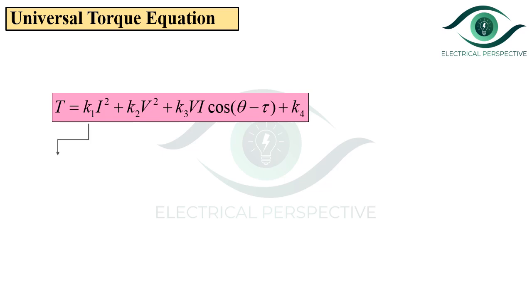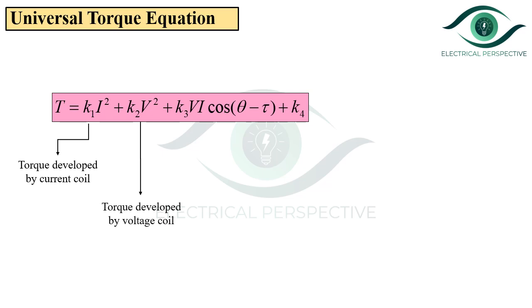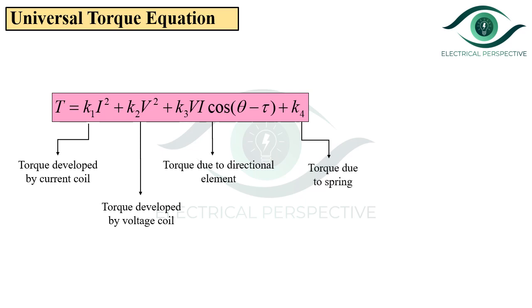Here, K1·I² is the torque developed by the current coil, K2·V² is the torque developed by the voltage coil, K3·VI·cos(θ − τ) is the torque due to the directional element, and K4 is the torque due to the spring. Here θ is the angle between V and I, and τ is the maximum torque angle.